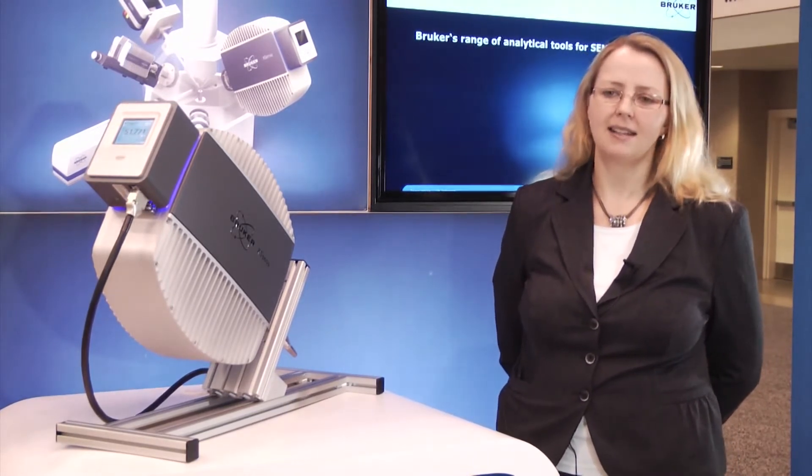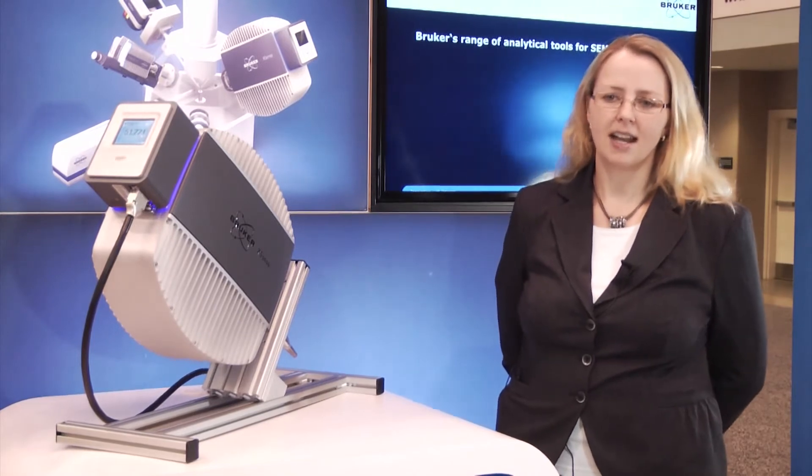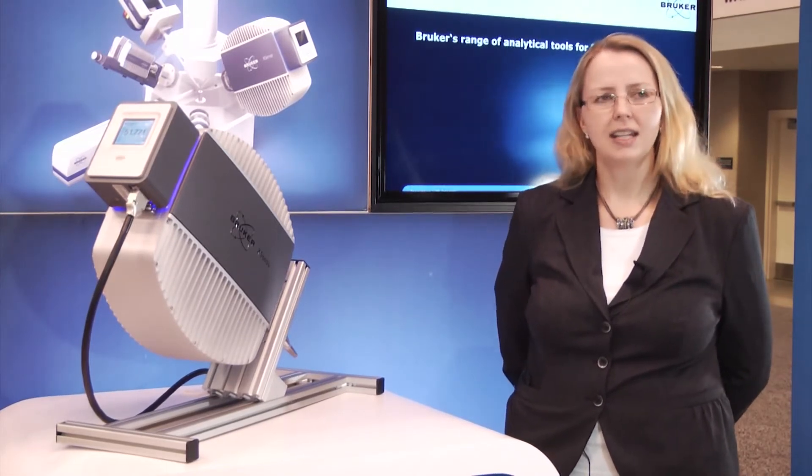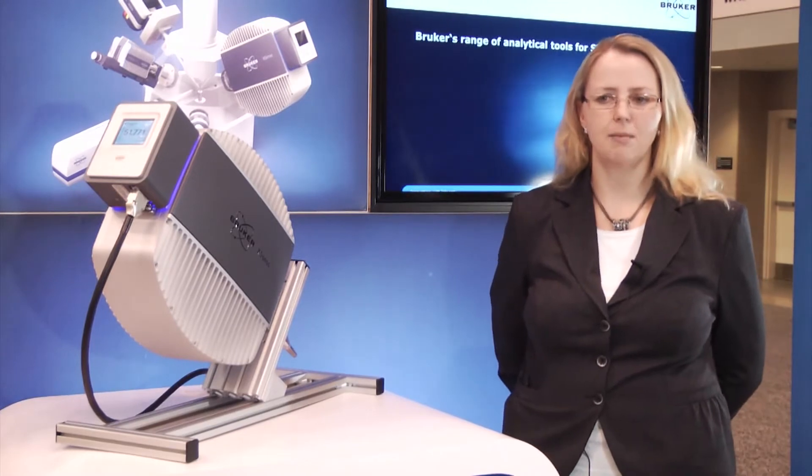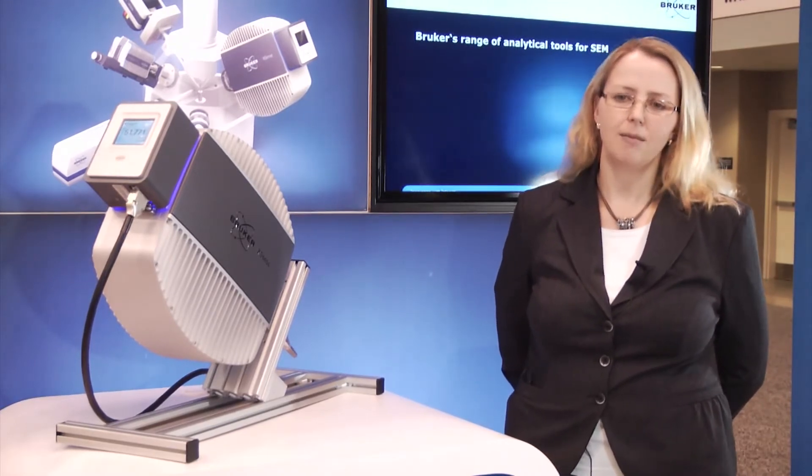Compared to electron excited spectrometry, Micro X-RF has the advantage of 20 to 50 times better sensitivity for trace elements in the mid to heavy element range.